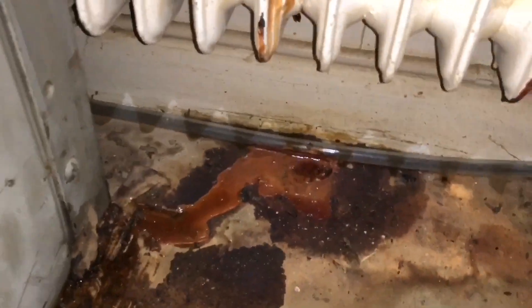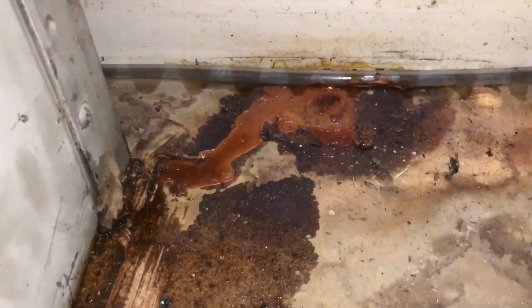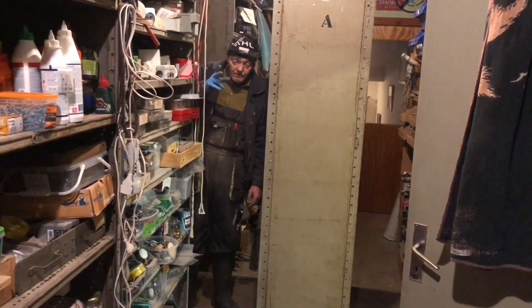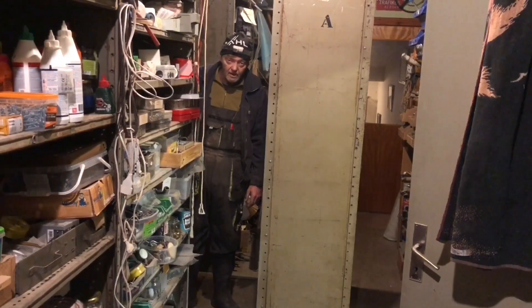This one in the middle is hot. So one out of four is working. That's wet — we've got a leaking radiator. Rusted out, as so many of them are. So the fact that the one directly behind here is working and the ones further along aren't means it's not air locked like I thought. I bled the radiators and there's water right to the top, but it has no glycol in it — which means these haven't circulated since I filled the system. That's bad as well.